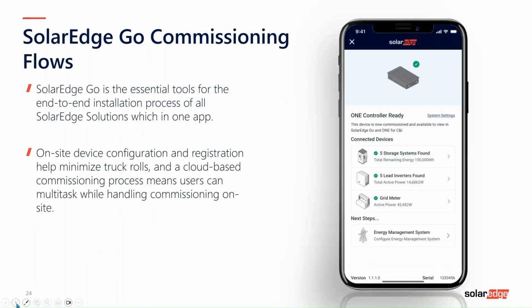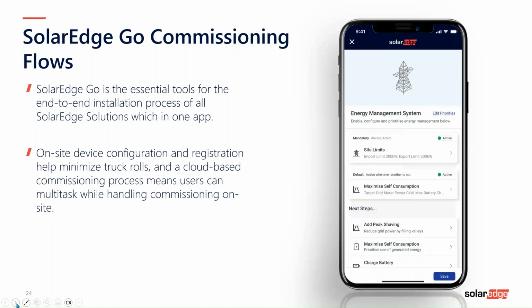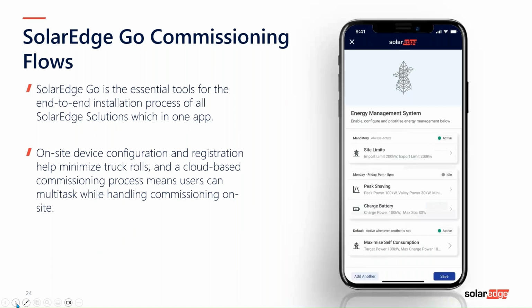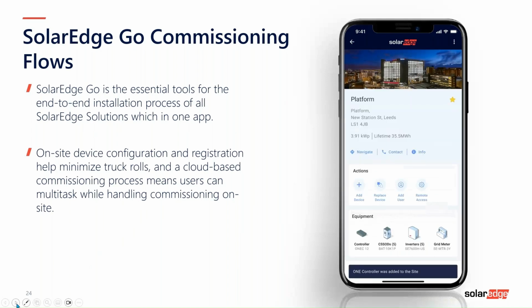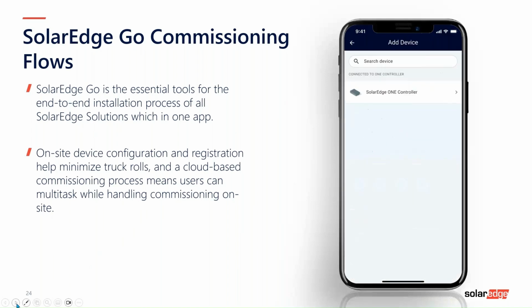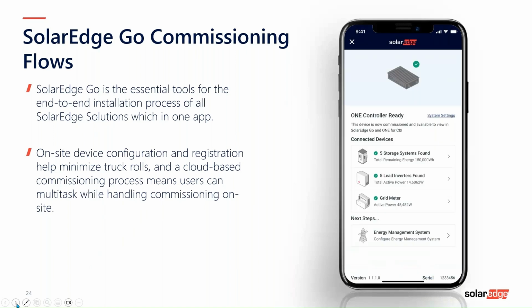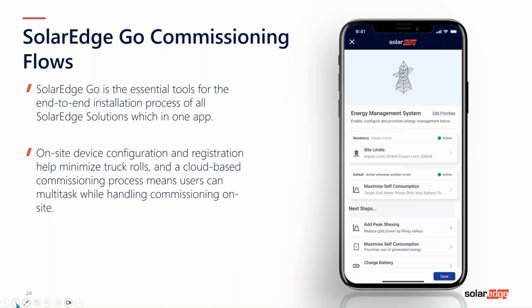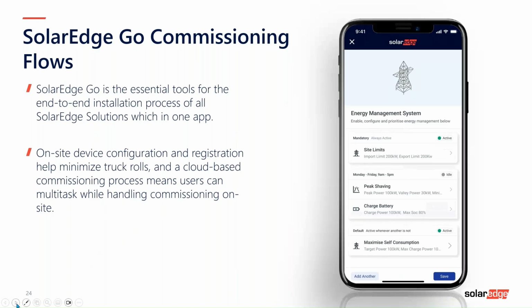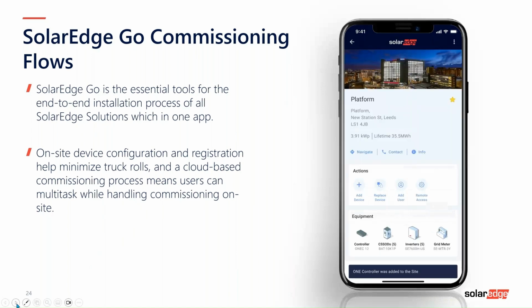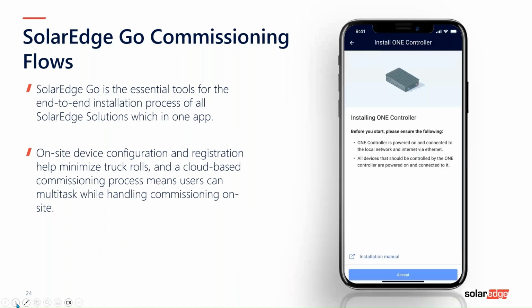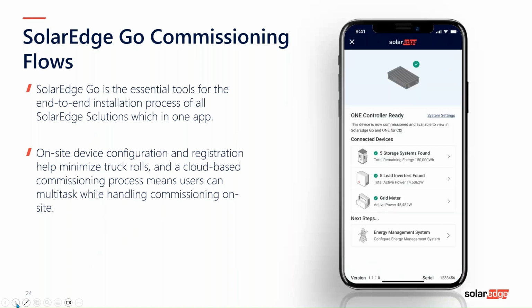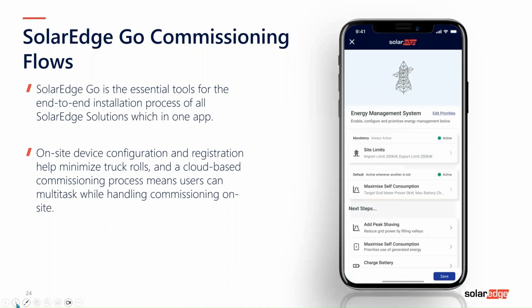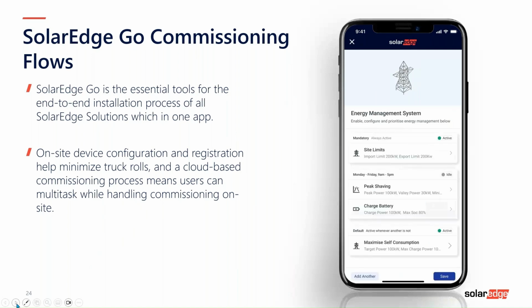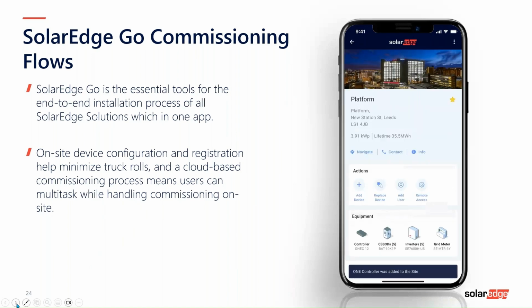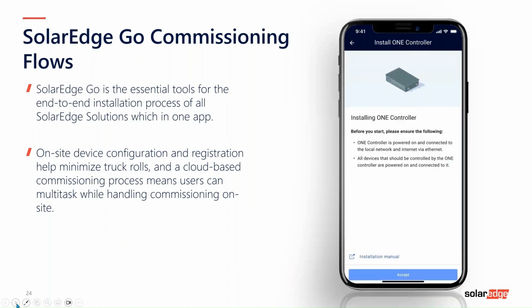So what we've got here is it's going through the commissioning options. Basically, SolarEdge Go is the device you need. Use the SolarEdge Go tool, don't use Setup, because Setup is going to end of life, and that will make your life a lot easier. The beauty of this is you can access remotely, so you can remotely access the devices on the site, the one controller, the inverters. You can do everything on there. And if you make every inverter a leader, you'll be able to connect directly to each inverter as well.